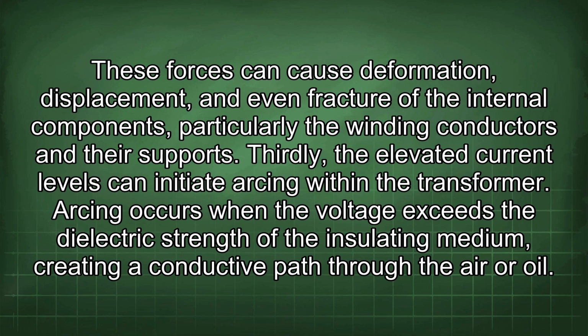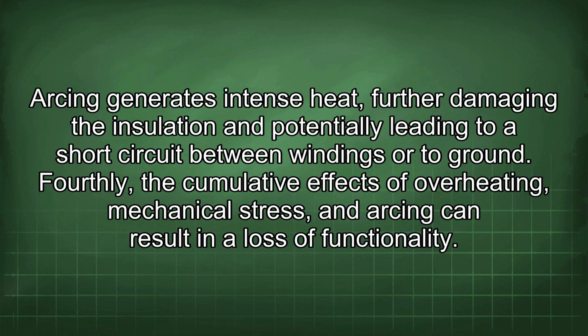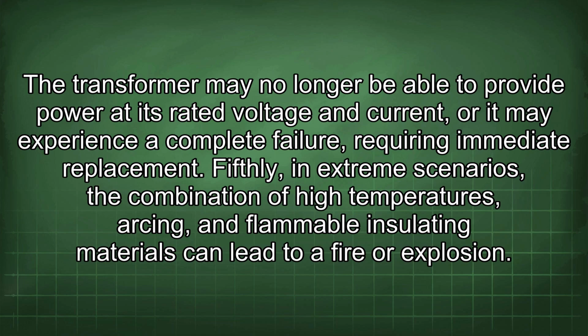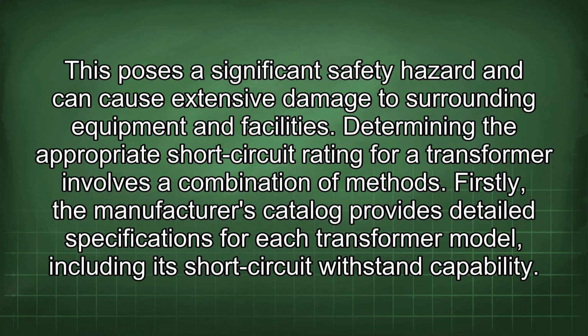Thirdly, the elevated current levels can initiate arcing within the transformer. Arcing occurs when the voltage exceeds the dielectric strength of the insulating medium, creating a conductive path through the air or oil. Arcing generates intense heat, further damaging the insulation and potentially leading to a short circuit between windings or to ground. Fourthly, the cumulative effects of overheating, mechanical stress, and arcing can result in a loss of functionality. The transformer may no longer be able to provide power at its rated voltage and current, or it may experience a complete failure, requiring immediate replacement. Fifthly, in extreme scenarios, the combination of high temperatures, arcing, and flammable insulating materials can lead to a fire or explosion. This poses a significant safety hazard and can cause extensive damage to surrounding equipment and facilities.